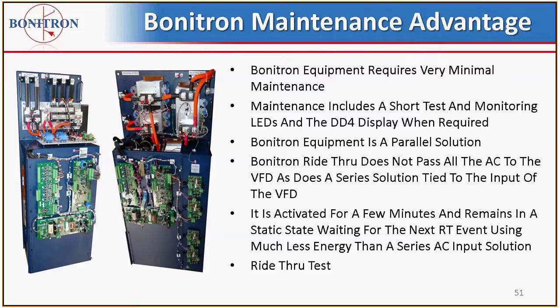As we have repeated numerous times, the Bonitron equipment requires very minimal maintenance. Connectivity is simple. Even the modules, if you get a modular system, the connectivity is pretty simple and very well defined in the manuals. It doesn't take any kind of programming unless you want to change some of the parameters, which are factory set and don't usually need any changing because we've already set it up for the type of system that you're requiring and to your specification. So usually everything is set correctly, and very seldom do we have to go in and adjust potentiometers or anything like that when a new system is installed.